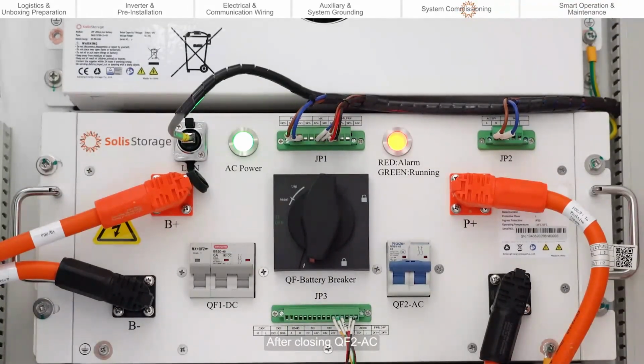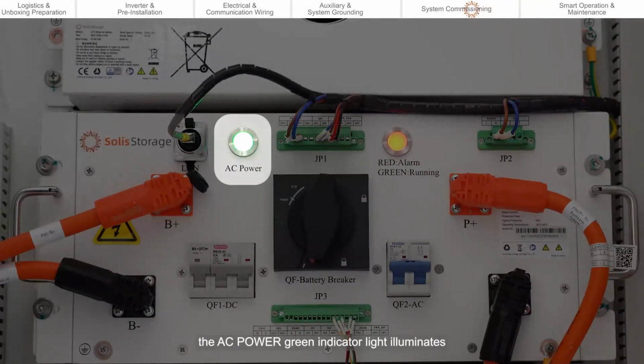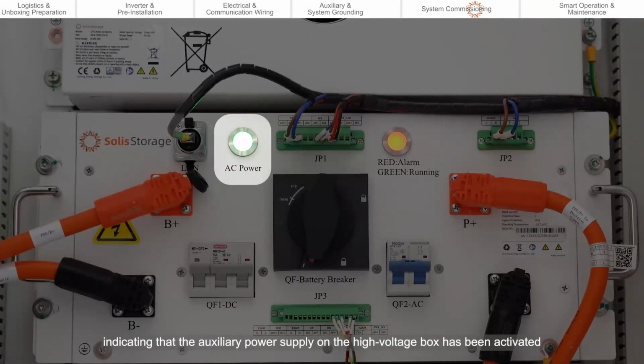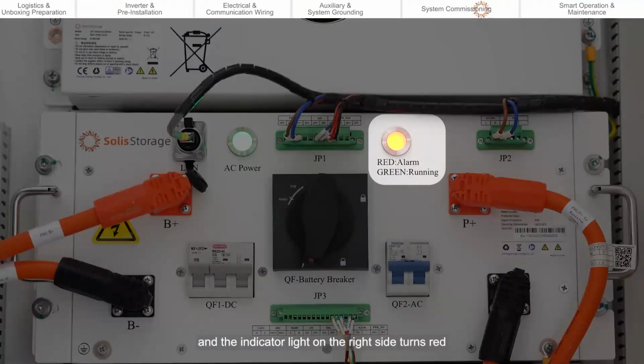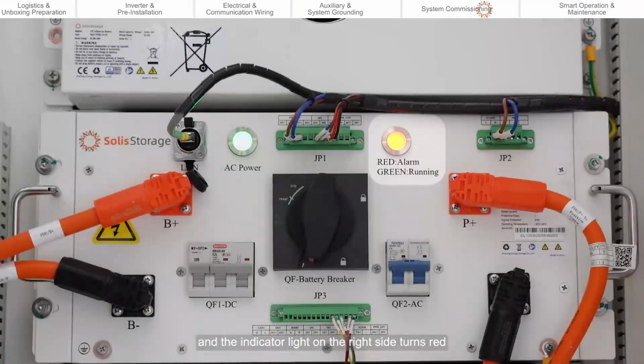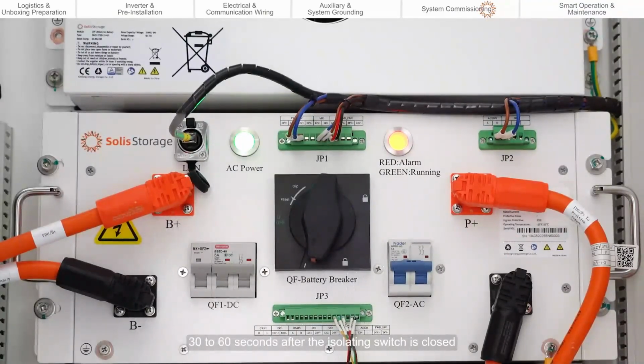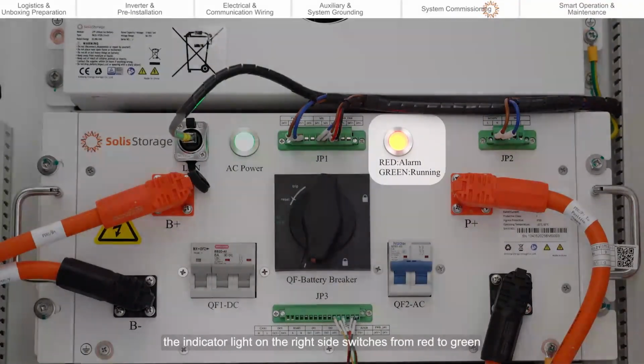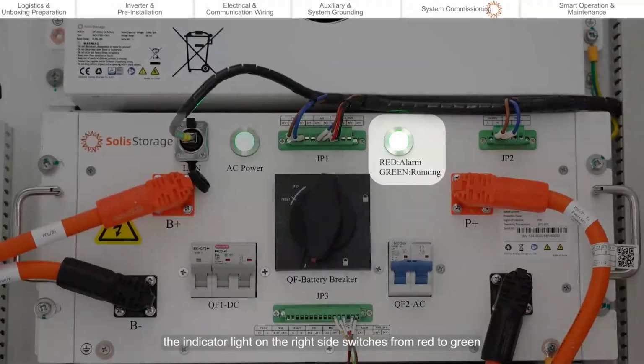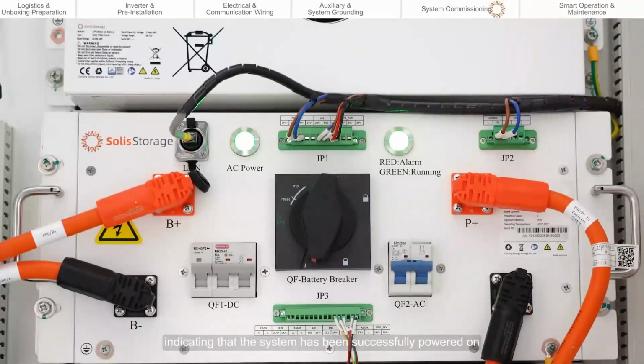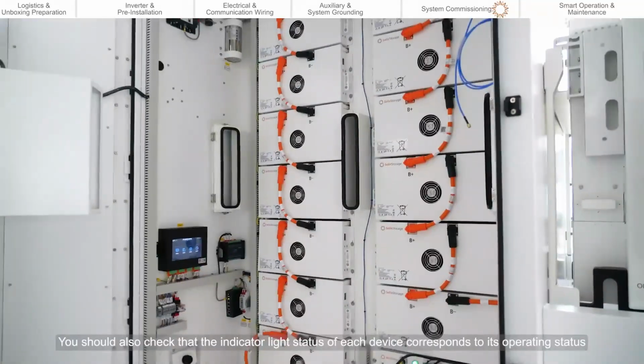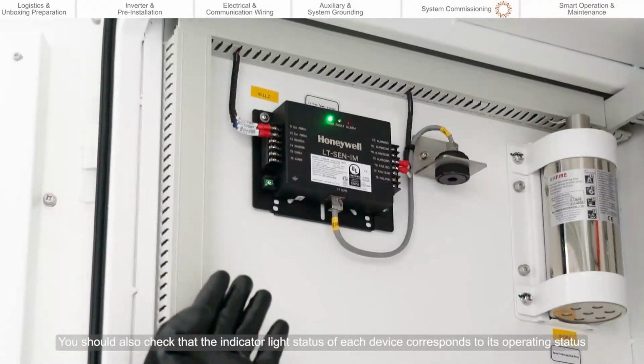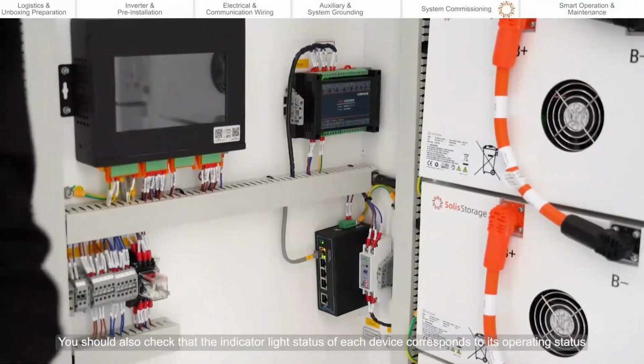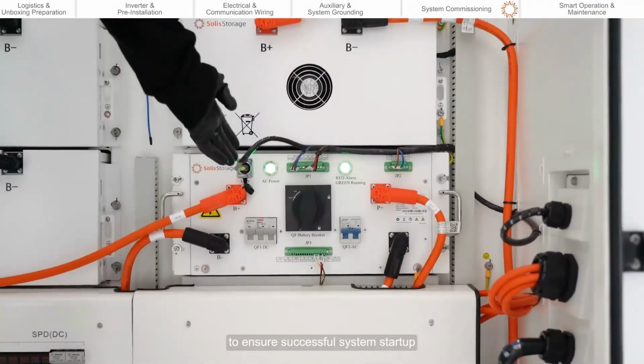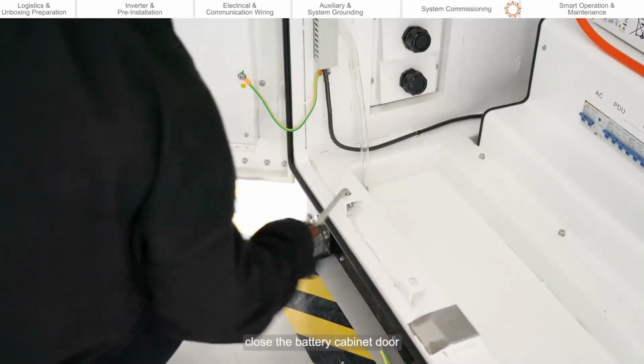After closing QF2 AC, the AC power green indicator light illuminates, indicating that the auxiliary power supply on the high voltage box has been activated. And the indicator light on the right side turns red. 30 to 60 seconds after the isolating switch is closed, the indicator light on the right side switches from red to green, indicating that the system has been successfully powered on. You should also check that the indicator light status of each device corresponds to its operating status to ensure successful system startup. Close the battery cabinet door.